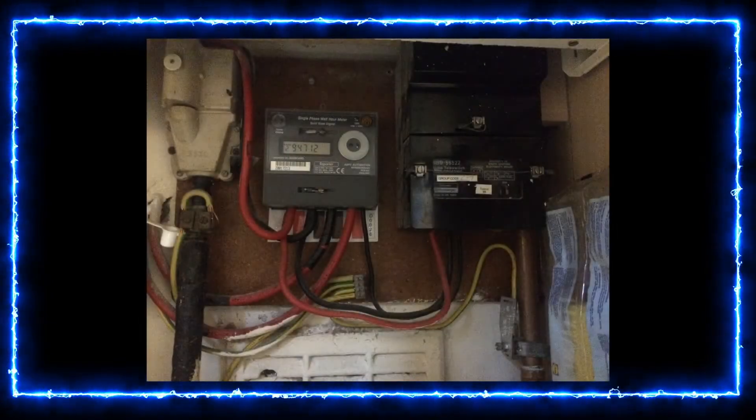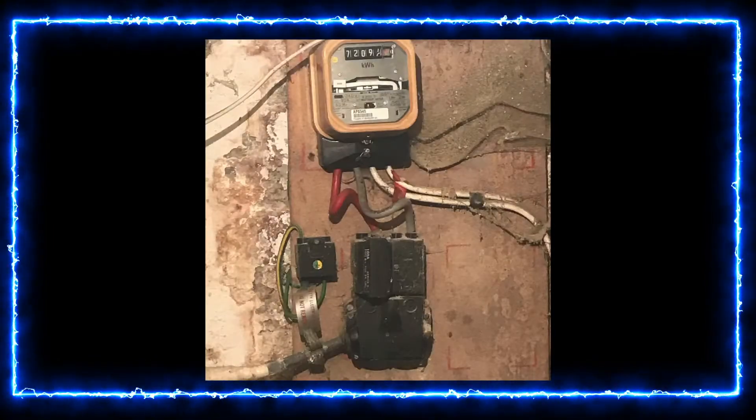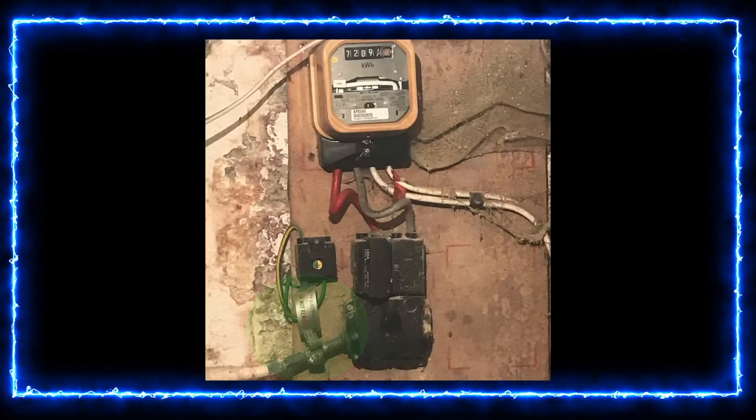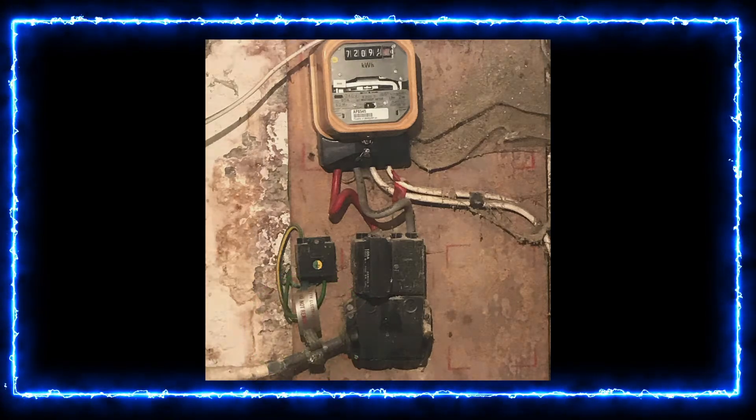Here's a few examples. You can see that the earth cable, the green and yellow cable, connects directly onto the sheathing of the supply cable. This is what you're looking for when identifying a client's earthing arrangements. Thank you.